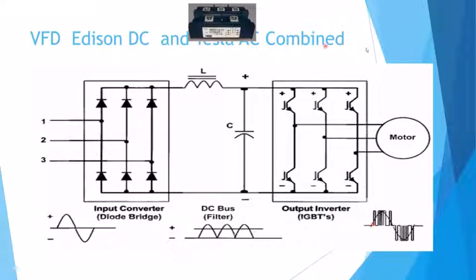But all that has to do with the more you fire it, the more you fire those transistors, the larger they got to be, and the more heat that they'll produce. So they tend to want to keep the carrier frequency down, but that creates more noise, and on the backside, it's a little bit more detrimental to the motor.